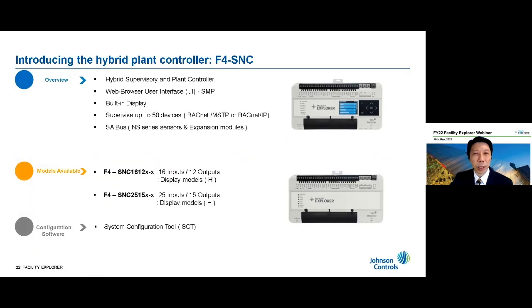So in the overview, the plant application is the target for that SNC and some small sites. They come with a web browser user interface, so the user can log in and edit and change logic over the web browser to make changes in the operation. We have different built-in integrated display options. We have different capacity to supervise some MSTP field devices on the field bus, either through MSTP or BACnet IP. It also supports the sensor actuator bus, SA bus, which allows us to connect network sensors and some expansion I/O modules to expand the I/O capacity.